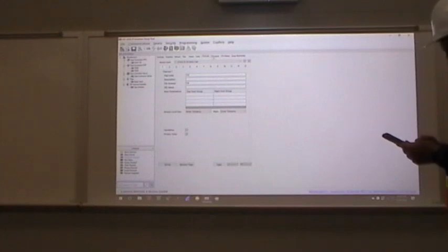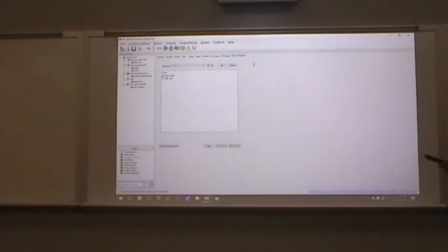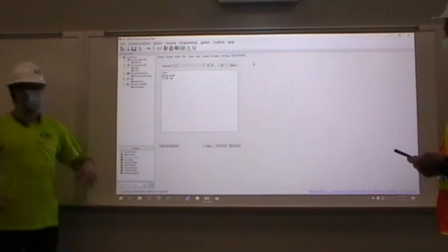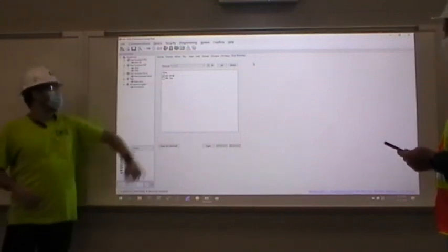And when we get into channels, these are all of the individual zones going out from that. There are relay inputs on these cards that can be used to activate messages. And then there's relay outputs that when activated can close a contact to activate something else. And then there's the group membership. Right now you guys have just requested an all call for the whole building. So that's all we have set up right now in the groups.